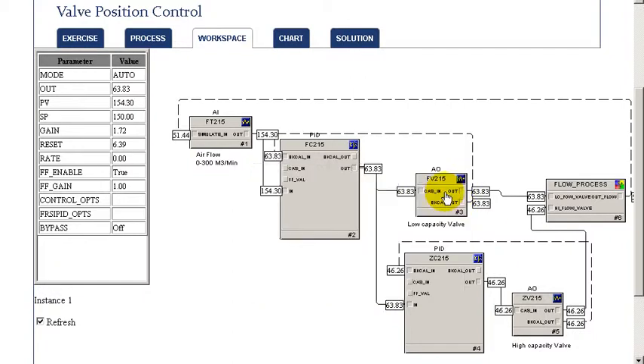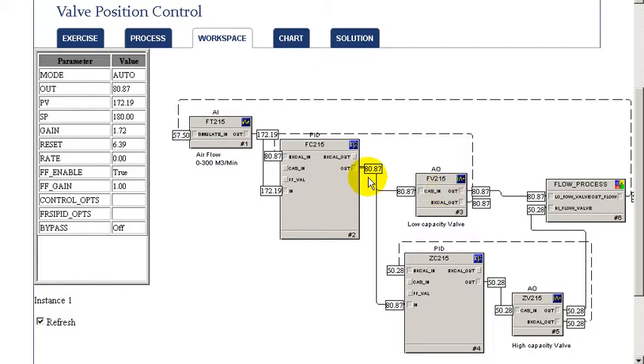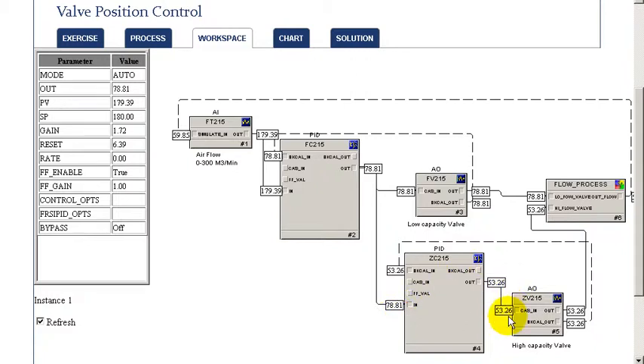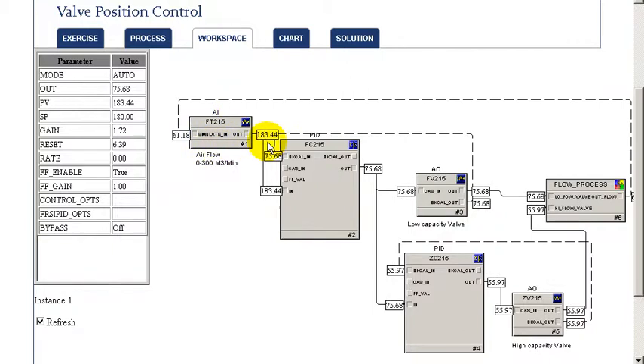We can change it one more time to 60% of scale or 180. And in this case, again, we see the smaller valve immediately respond to this to allow us to get it quickly to our target value. And gradually, the larger valve starts to move to keep our smaller valve within range and to keep it longer term at a target position.